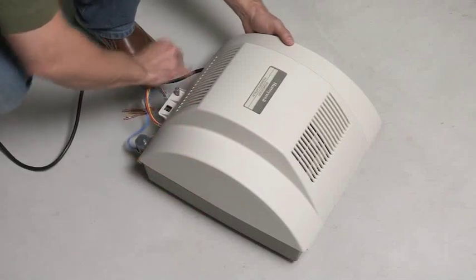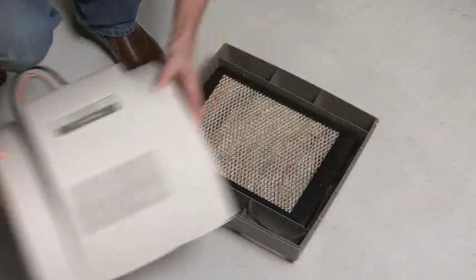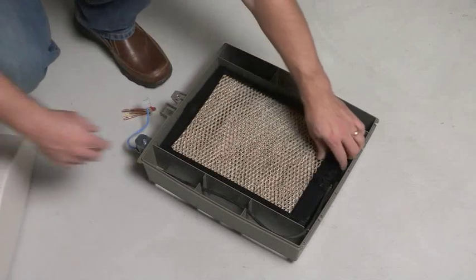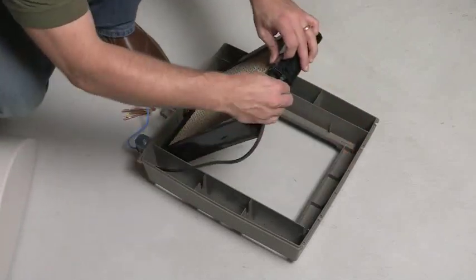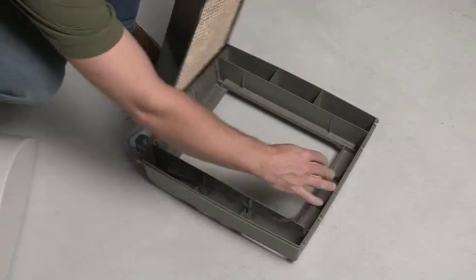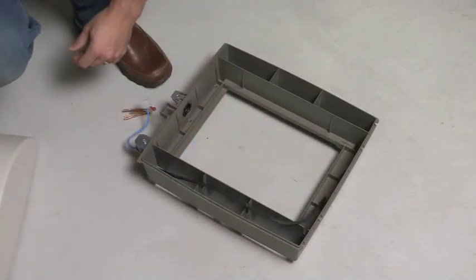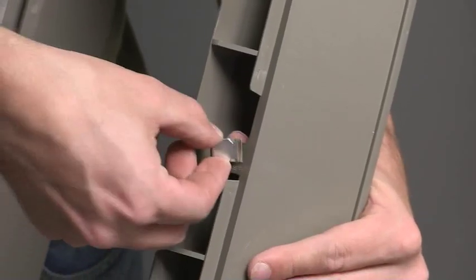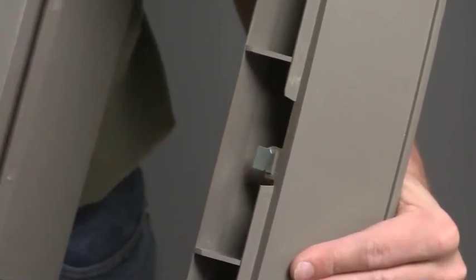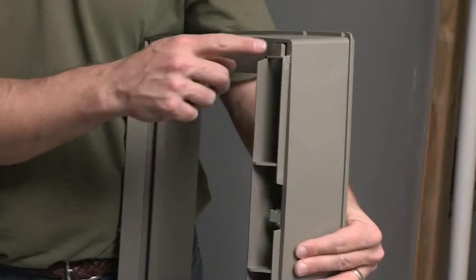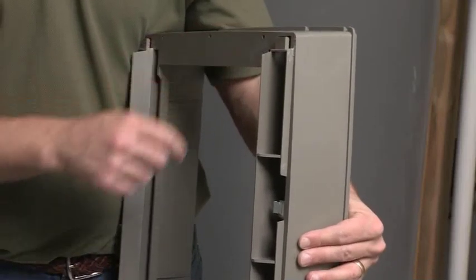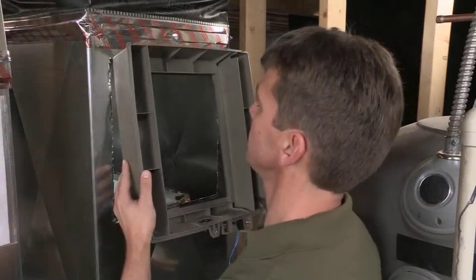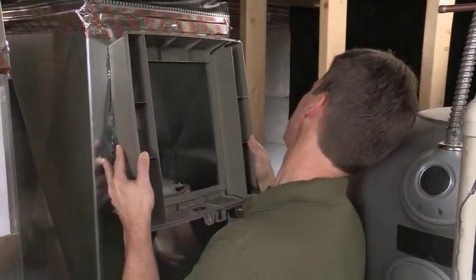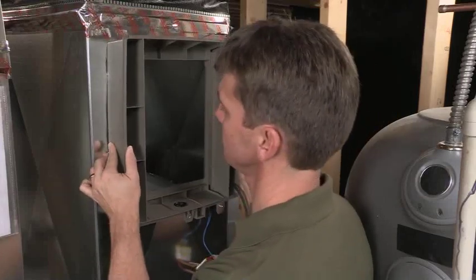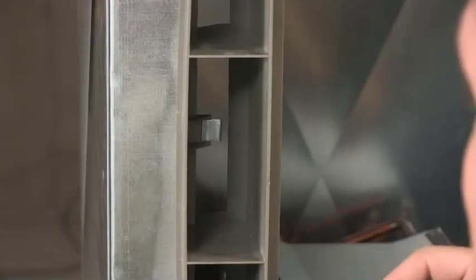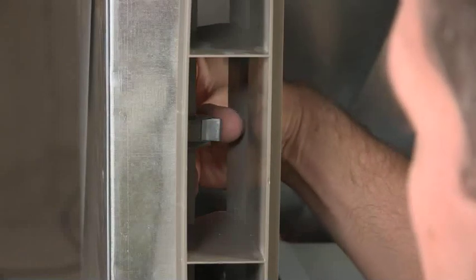Remove the cover on your humidifier and the pad so that the housing can be placed in the opening first. When removing the pad assembly, gently detach the water feed tube from the pad frame by pulling the end of the tube. Add the securing clip as shown, but don't put it on all the way quite yet. Locate the plastic tabs, then position the frame on the upper edge of the opening. Push in the securing clips until they are completely seated.